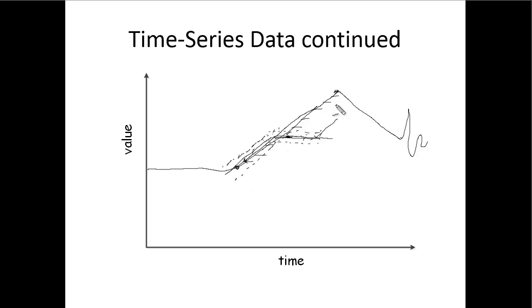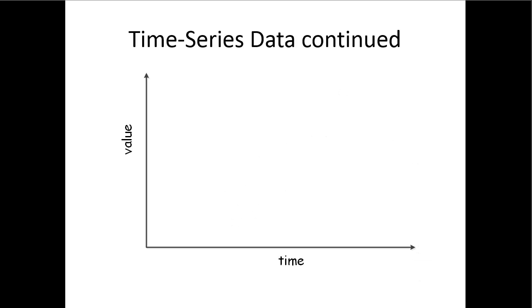Okay, so this is called the swinging door algorithm, and what it is it's just a way of taking my signal as it comes in, and during times when it's relatively linear and uninteresting, I'm not taking a whole lot of readings. But again, when something like this happens, I'm going to be taking a bunch of readings here because the slope of the line's changing all over the place. Okay, so this is kind of cool because what's going to happen is when I read my stuff back from the database, I'm going to end up reading back points, say something like this.